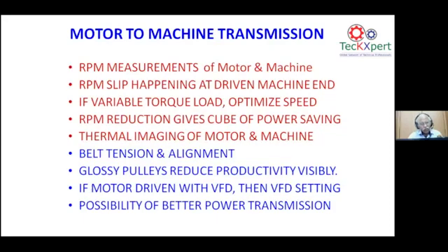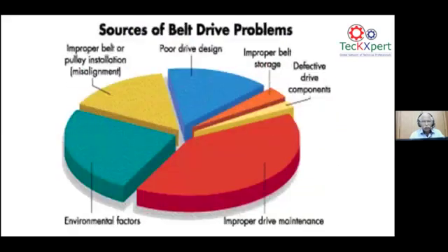So RPM reduction on a variable torque load is very much important, but on a constant torque load, where all our production machines are, you can see it by improving this, by reducing the slippage and improving the motor to machine transmission by optimizing the speed ratio of the pulleys. At the same time, optimizing the speed ratio, and the V belts are changed to cogged belts. Automatically, this improves the motor efficiency and the productivity efficiency also.